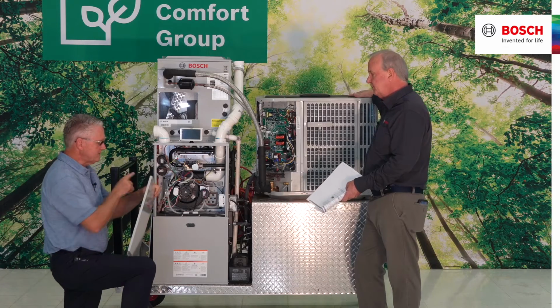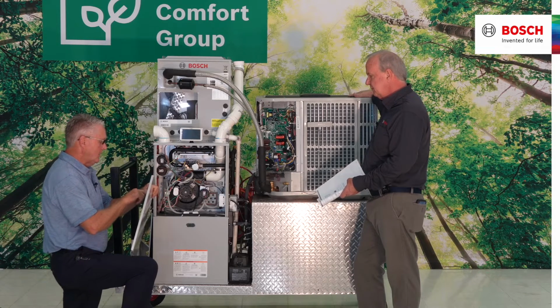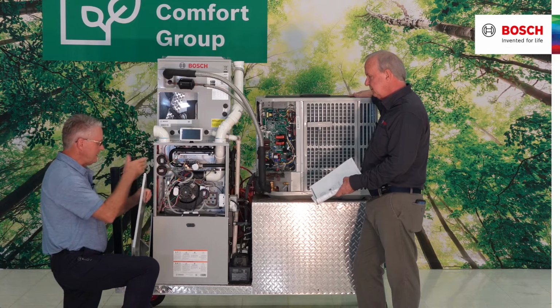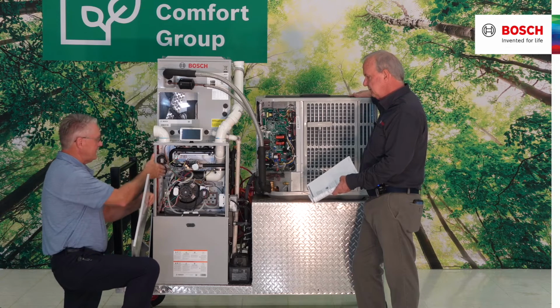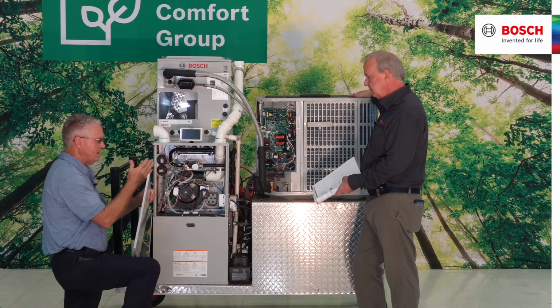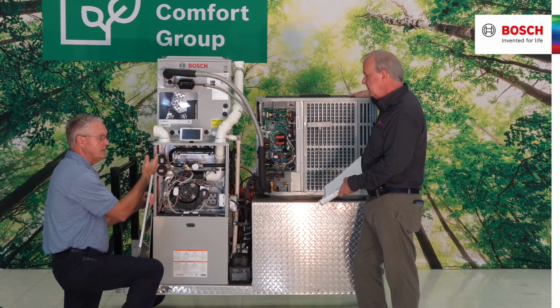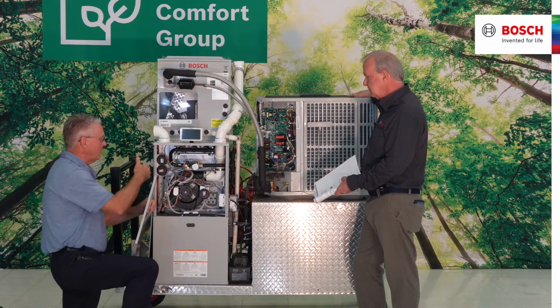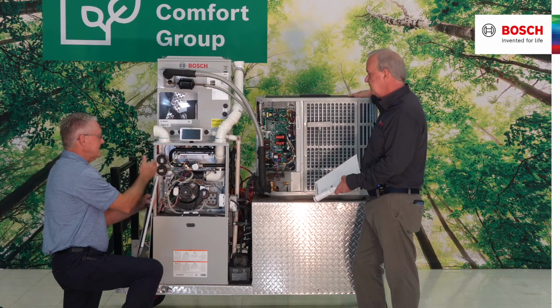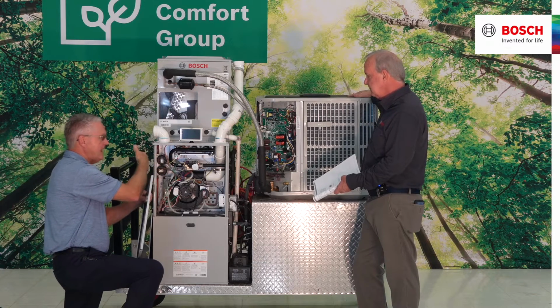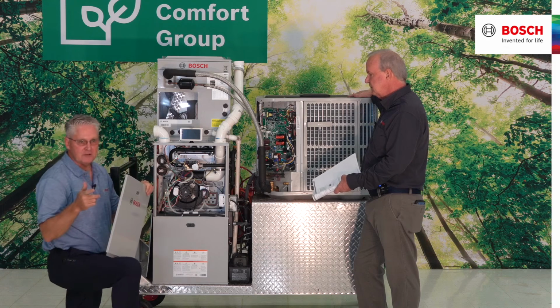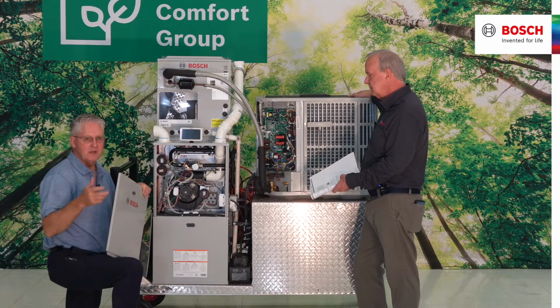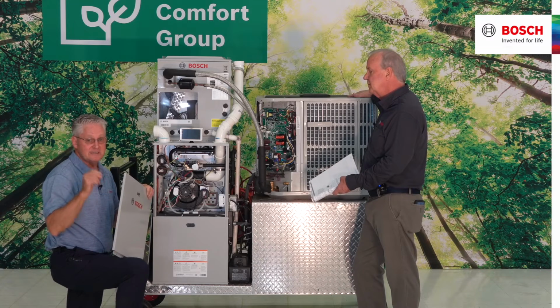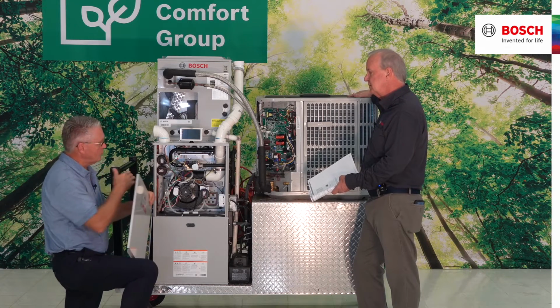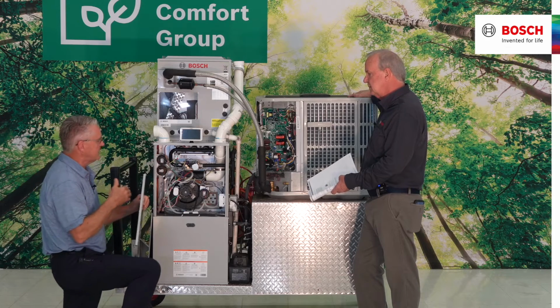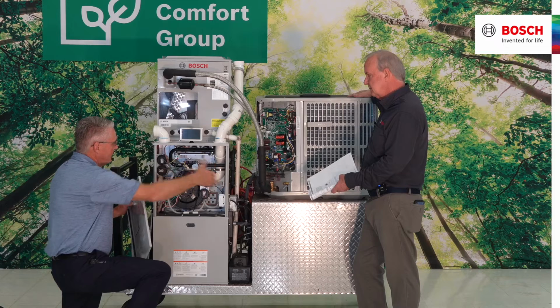Great question. So this is a BGH96M 060B 3B. In the 060, again, that's the BTUs for the output of the machine, okay? And the B stands for the width of the cabinetry. So this is a 17.5, or 17 and a half, wide furnace. The 80,000 is also going to come in the B width, but it also comes in the C width. So the C represents a 21-inch wide furnace, and the D represents a 24.5 width furnace.